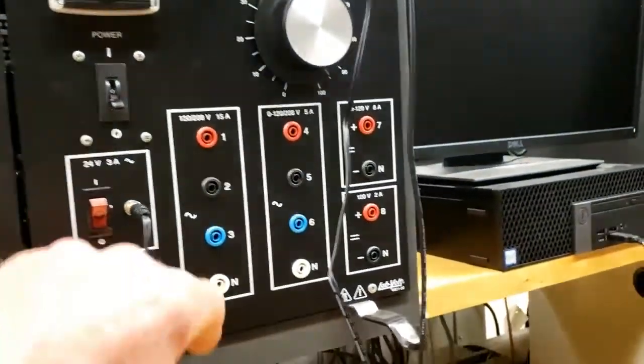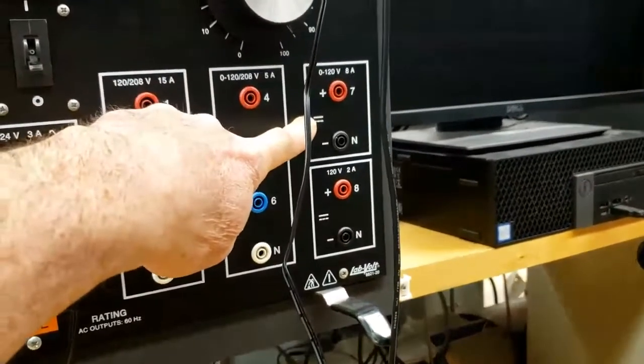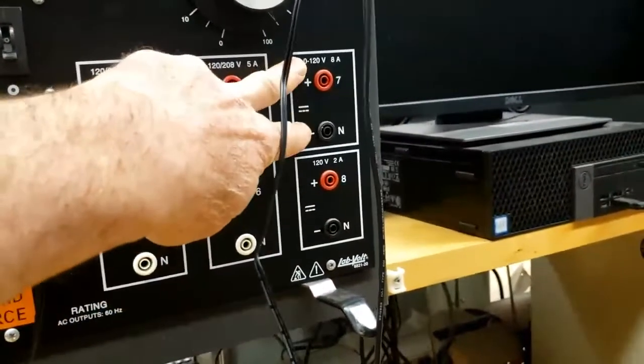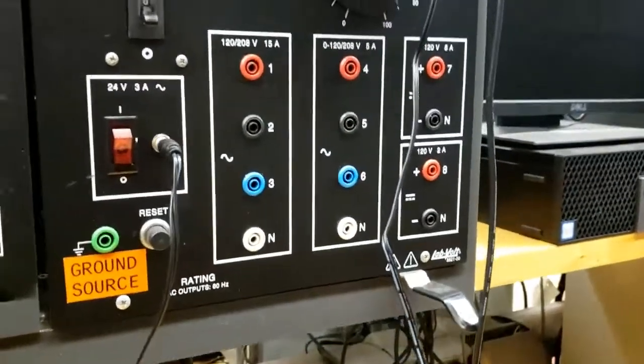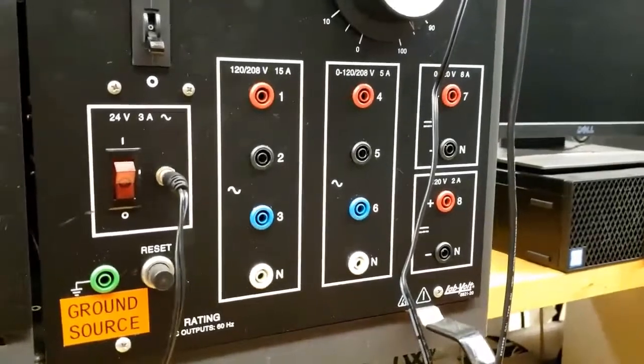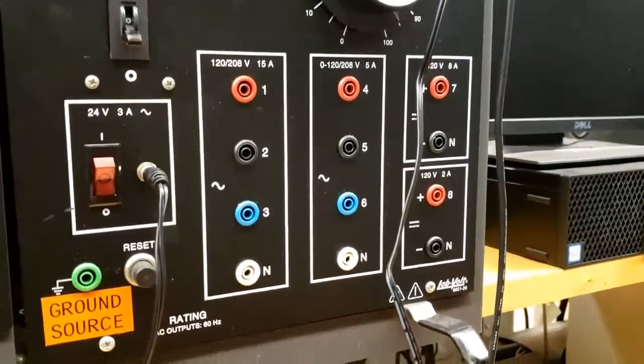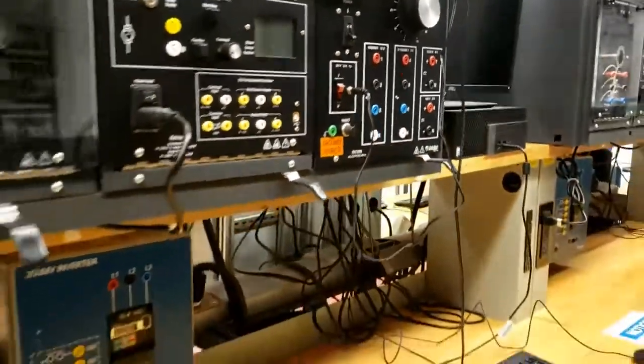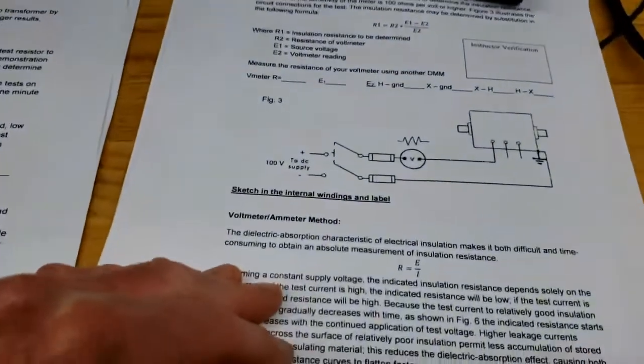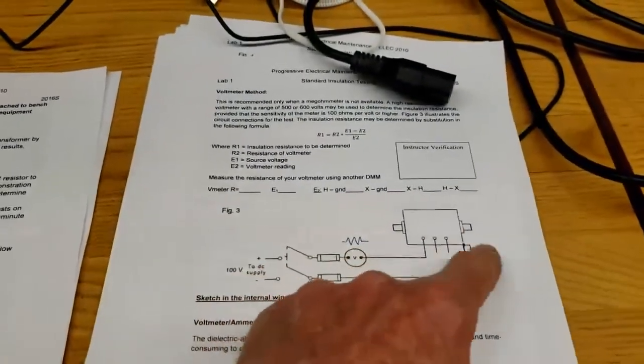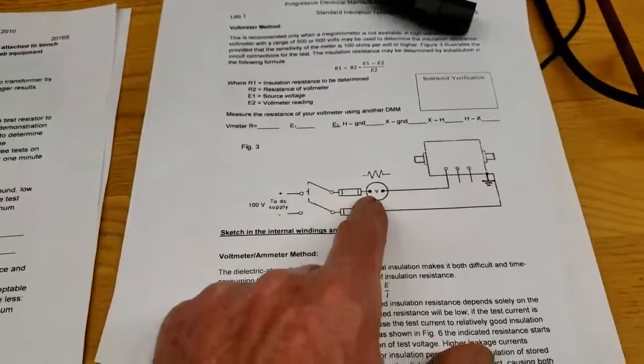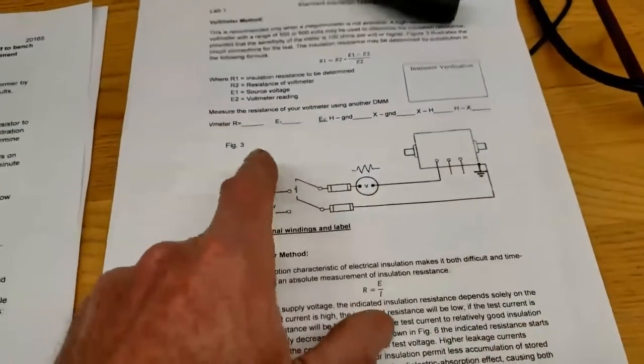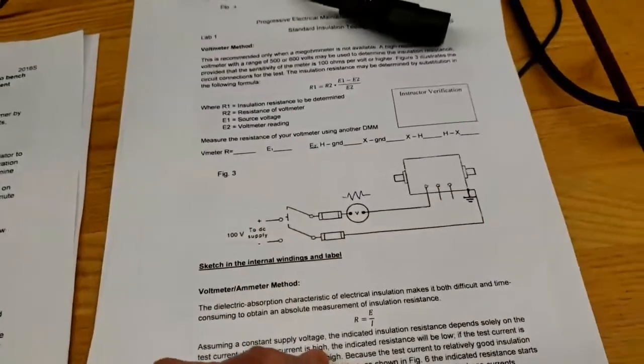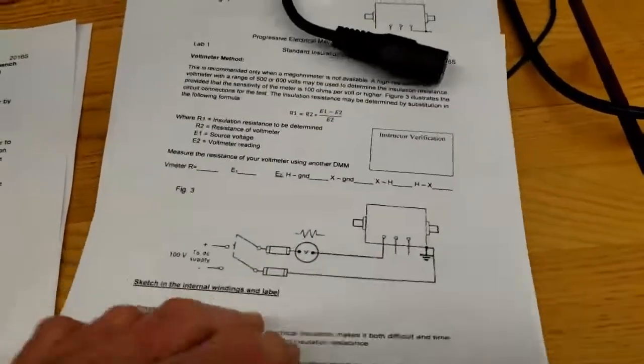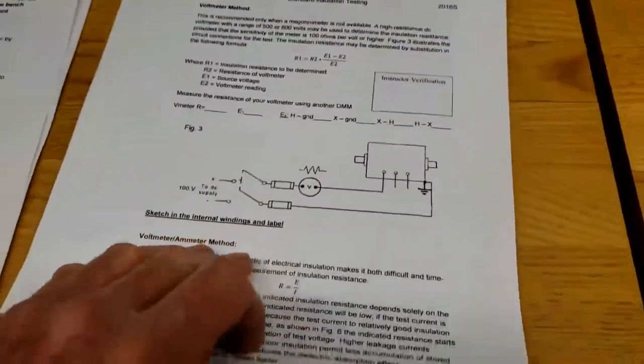You can follow them. Here's our standard power supply. We can use the adjustable DC. This is all AC, don't use that. And you're going to set it, put a meter on there, hang a meter off there before you take your leads off, and leave it there so you can just tweak the voltage to exactly 100. If it isn't 100, just record what it is so you can get as close as you can. So then when you put voltage, you're going to see how much current flows with an 11 meg ohm resistor in here. From that, doing the math to determine the resistance. You know the voltage, you know the current, you can calculate the resistance using Ohm's law. That is the ohmmeter method, or voltmeter method.